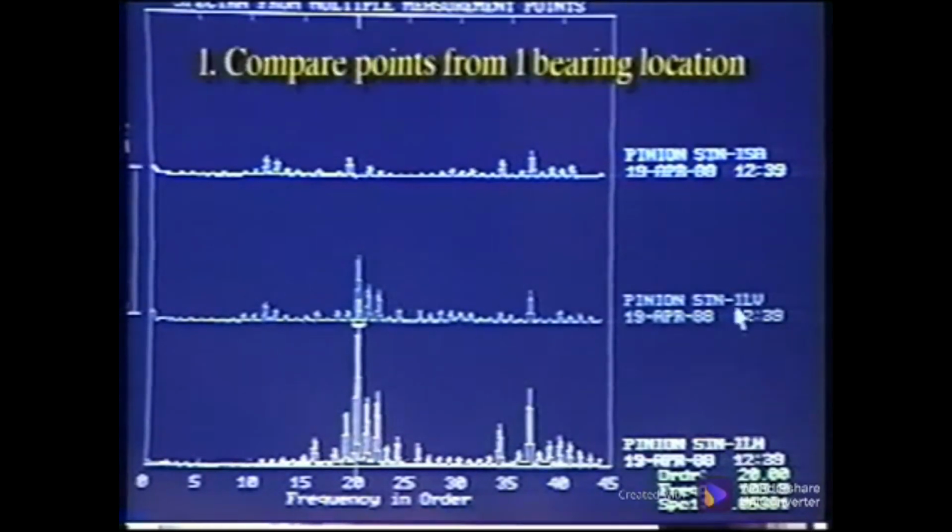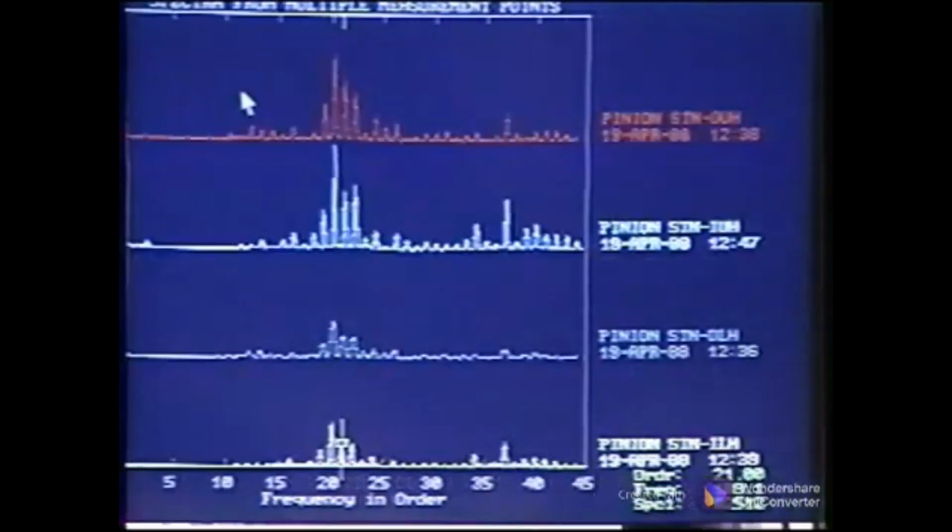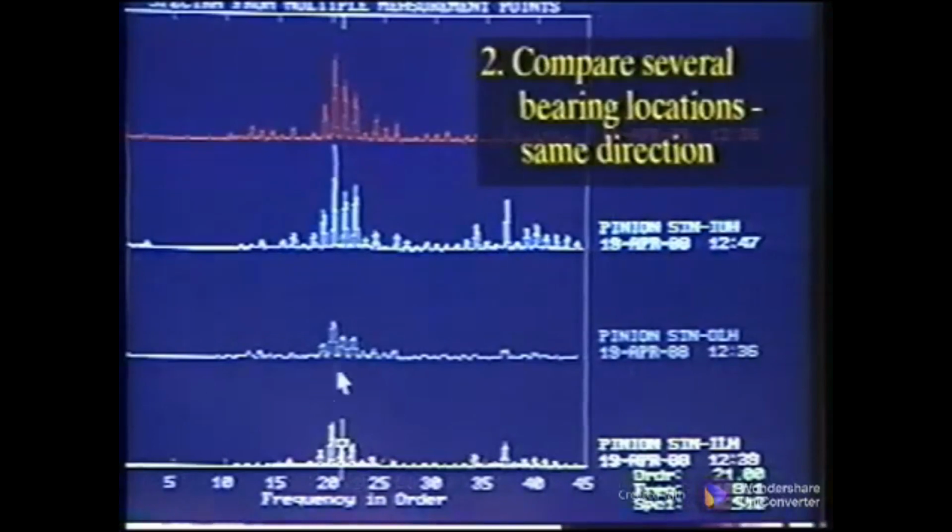Compare the measurement points from one bearing location and select the ones with the highest amplitudes or most information. Next, compare points of the same direction from several bearing locations. This approach can help you zero in on the problem area and save time.